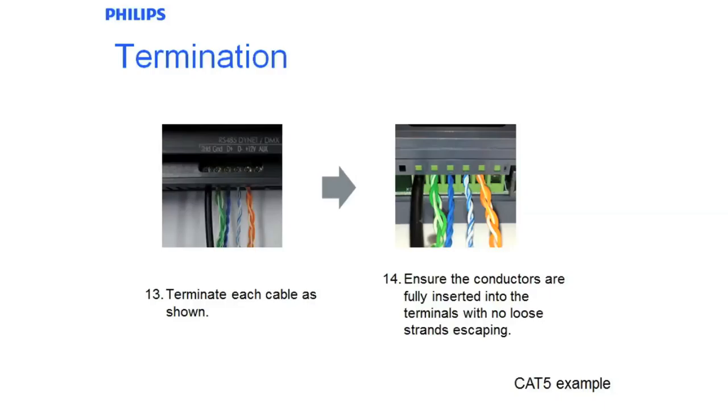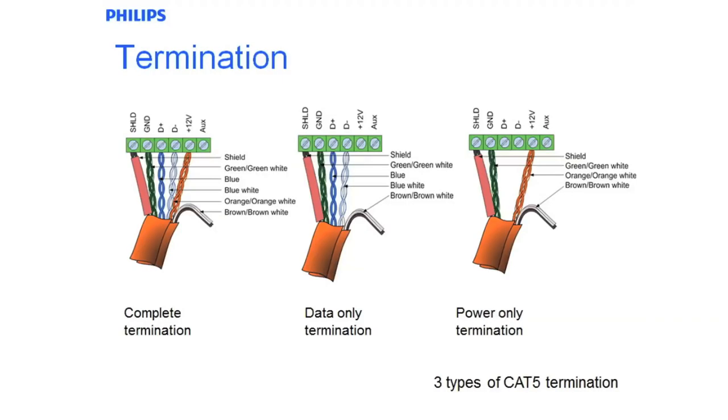The auxiliary connection is generally not used in most applications. There are three typical terminations which can be done depending on the application. The complete termination includes drain wire into the shield, green pairs into the ground, the blue of the blue pair into D-plus, the white of the blue pair into D-minus, the orange pair into plus-12, and the auxiliary terminal not used. With the Cat5, the spare pair is always not used. Just pull it back on itself and you can use it in future if required.